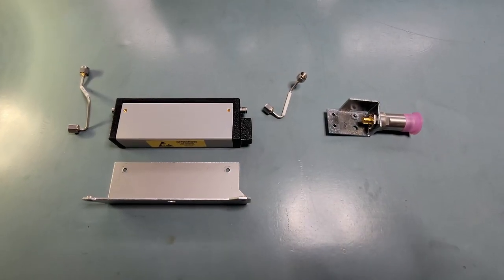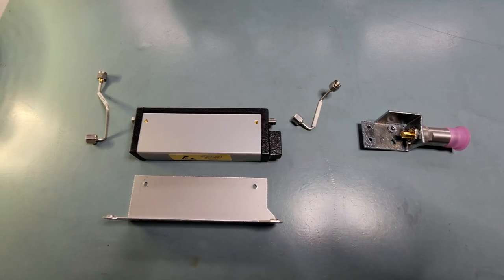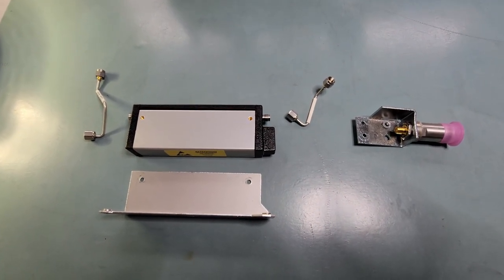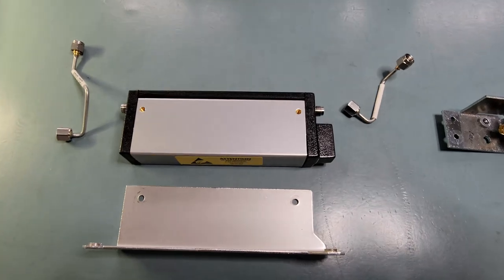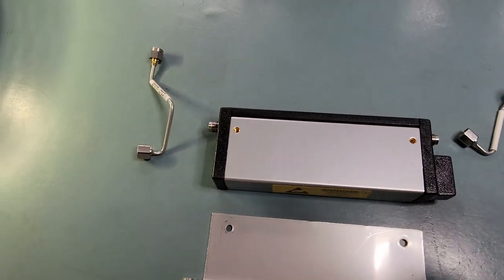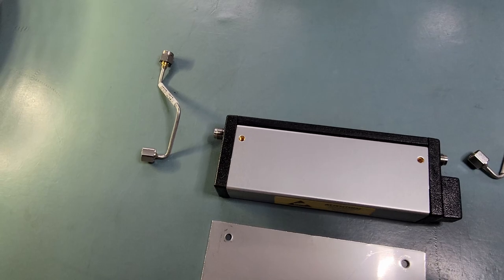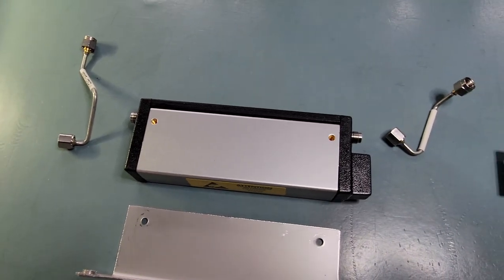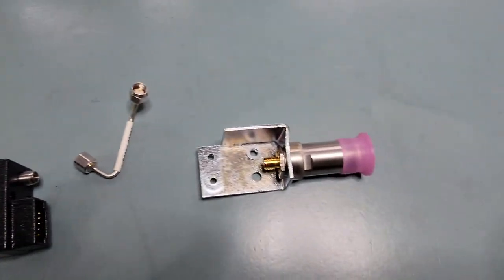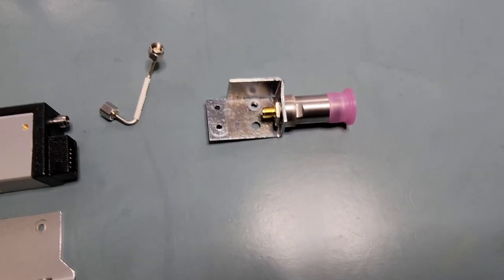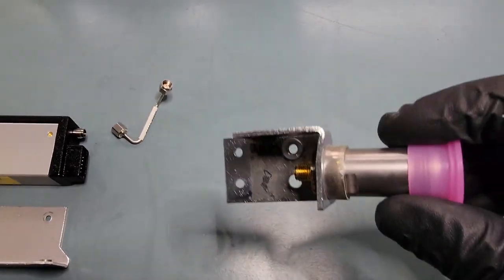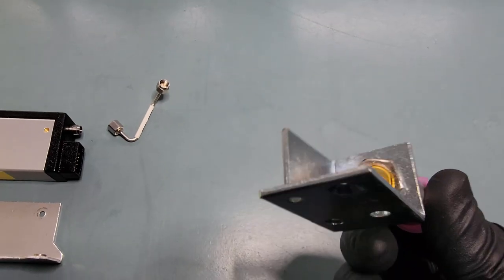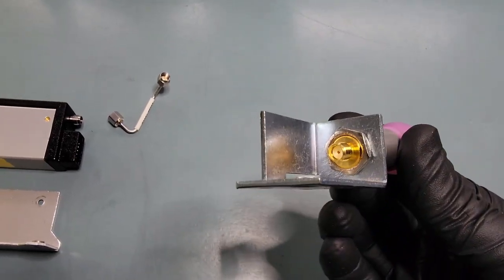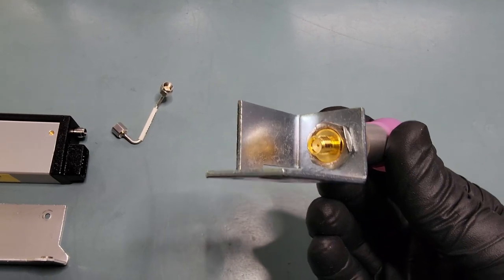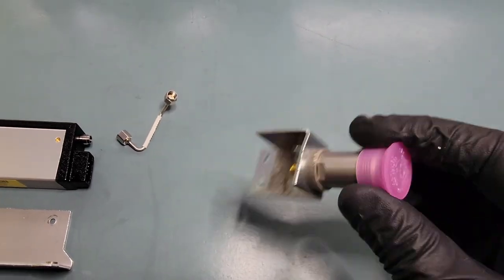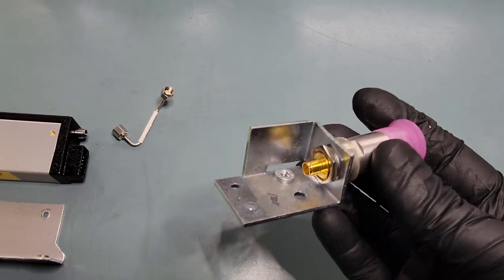Okay, so here are the first few bits that we removed that could be responsible for the low amplitude output. We have the step attenuator option, the semi-rigid cables that go from the output directional coupler to the attenuator, and then through the attenuator to the output connector on the front panel. And you can see the bracket is definitely bent here, so we can fix that. And this is just a PTFE type SMA connector. It's not a precision air dielectric or 3.5 millimeter connector.